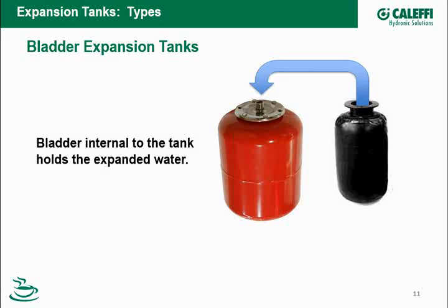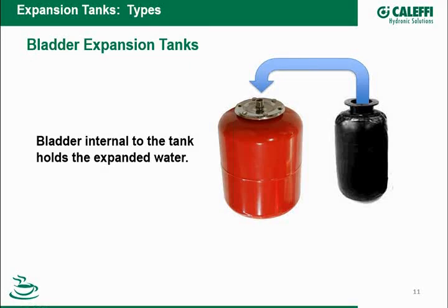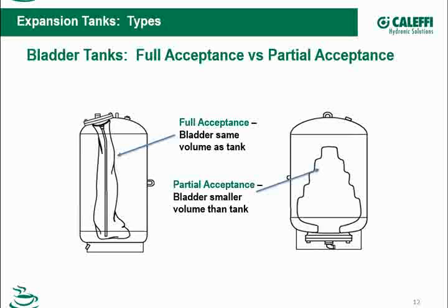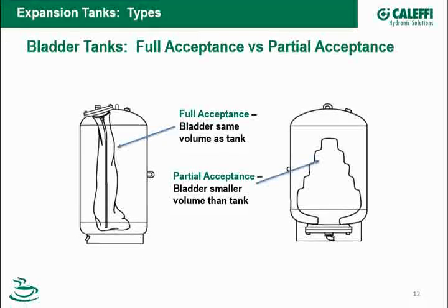Now the bladder tanks, you'll often see listed as either a full acceptance bladder or a partial acceptance bladder. This really describes the relationship between the volume of the bladder and the volume of the tank. So if I have a tank that's a full acceptance bladder, let's say it's a 500-gallon tank, the volume of the bladder is also 500 gallons. Whereas a partial acceptance tank, the bladder is some volume less than the full volume of the tank. So I may have a partial acceptance tank where the tank's volume is 500 gallons, but the bladder volume may only be 200 gallons.